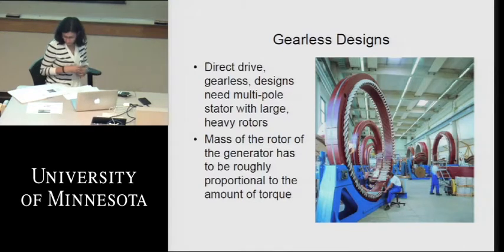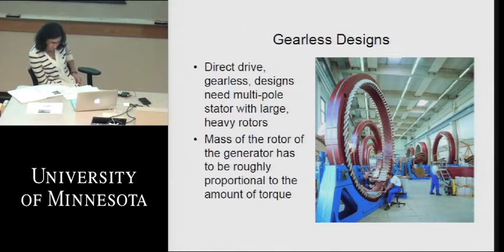But these generators for a gearless design have to have a large number of poles, because that generator is going to operate at the same speed as the rotor is rotating for the wind turbine. And the second point is that the mass of the rotor generally has to be proportional to the amount of torque. And so you get these very large rotors in this type of design, but they're very heavy.